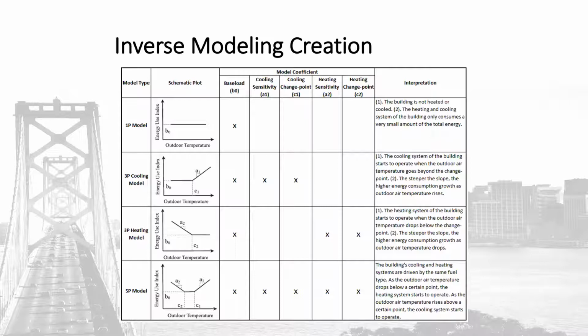In this model, Better is plotting along the x-axis average daily outdoor air temperature for the last 12 months, and along the y-axis average daily energy use intensity for the last 12 months, creating a plot, fitting a model, and then identifying the following 3 model coefficients: the base load, the cooling sensitive consumption, and the cooling change point. The horizontal portion, i.e. the base load, provides us with an indication of the level of performance of various base load systems in a building, such as the combination of light, plug loads, and process loads.